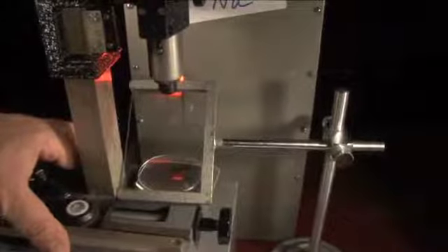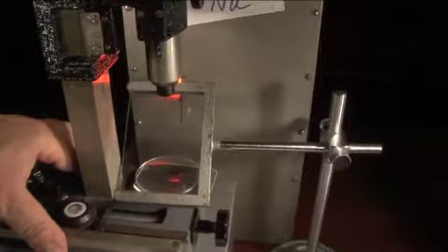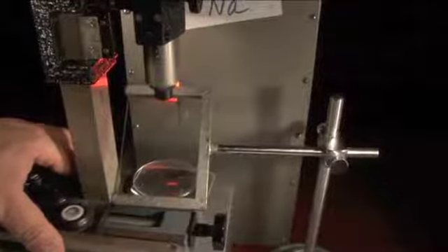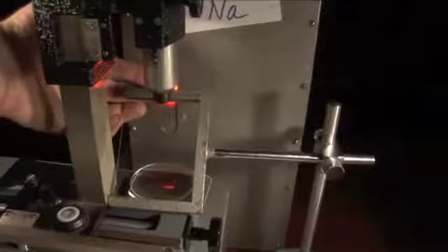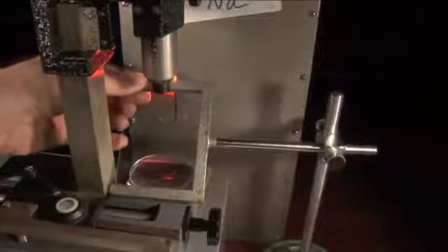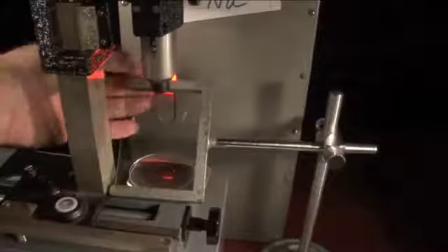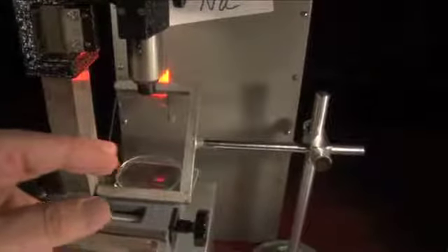You should be able to get really nice contrast, very bright rings and very dark rings. If you narrow this gap to about maybe 2 centimeters and you have the right angle for this glass reflector, just play with the angle, get the angle right, get the size of this gap right, make sure it's positioned exactly in line with the microscope, and you should be able to get really good contrast with the rings.